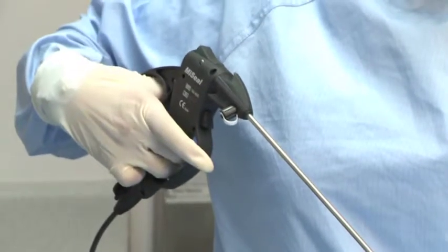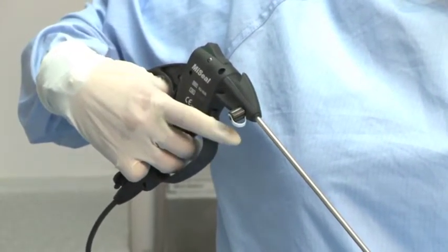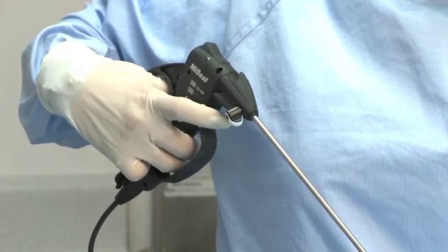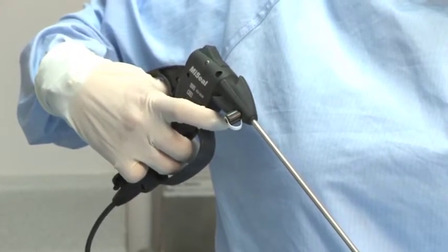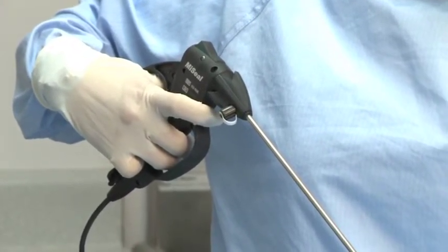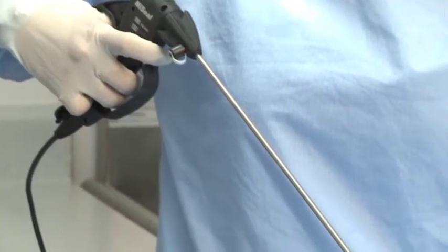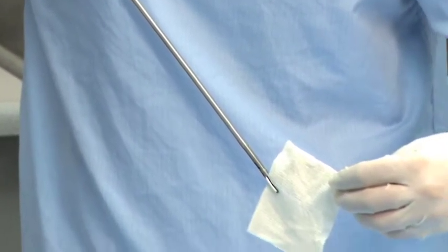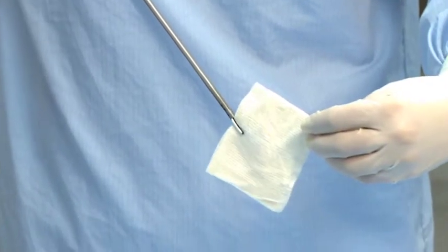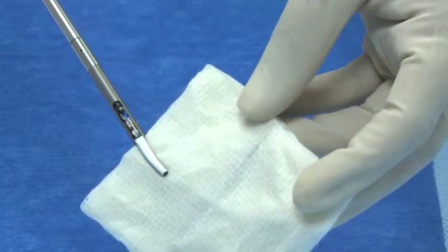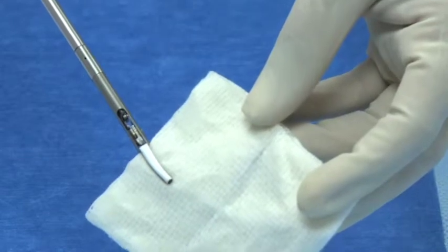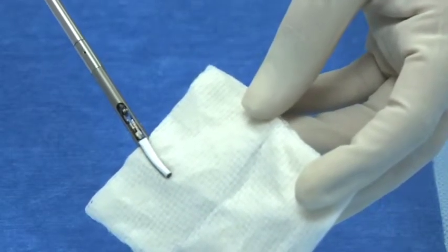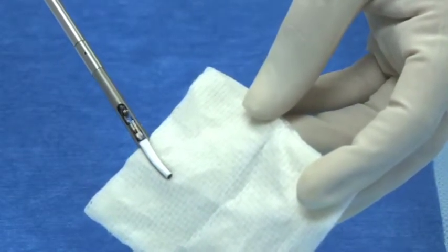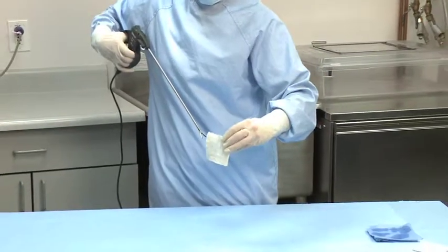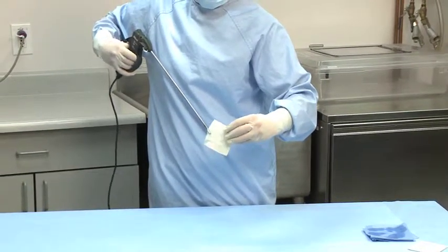Now it's time to depress the finger switch partially to the low setting. This switch allows the user to adjust the heat output via the power supply. A hissing sound from the gauze pad and a pulsing tone indicate the device is active in the low setting, or variable mode of the UPS. This mode is utilized when vessels are being sealed. If a constant tone is emitted and steam generated, the finger switch was depressed too far. Release the finger switch and try again.